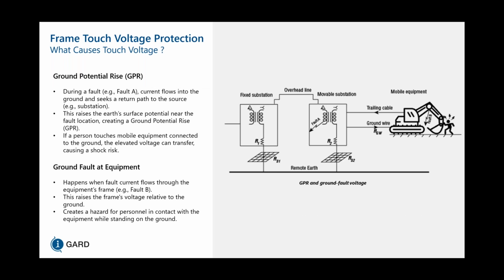So the first one is ground potential rise. Even if the fault is not contained within the system that you're connected to, let's say you have a fault on this in-between path between the fixed substation and a movable substation, and the fault is occurring on the primary of the transformer on the movable substation, this will create a ground potential rise in the location near the fault. And if a person touches the mobile equipment that is still connected to the same ground at remote Earth, then the person can experience an electrical shock.